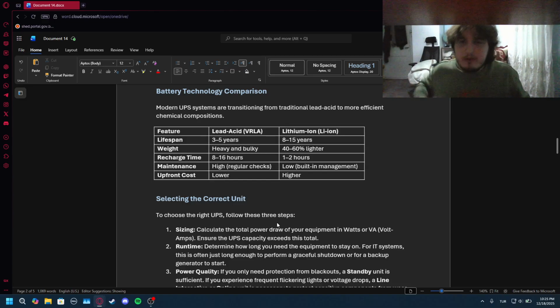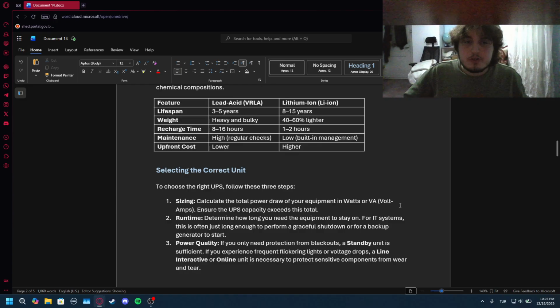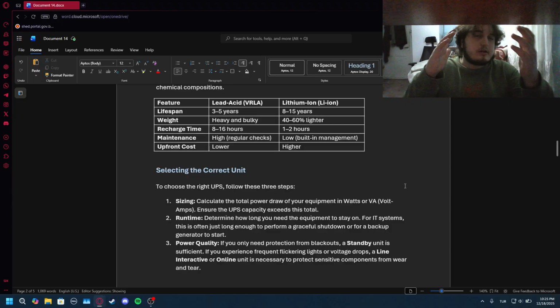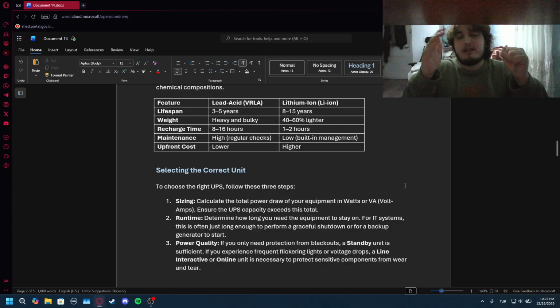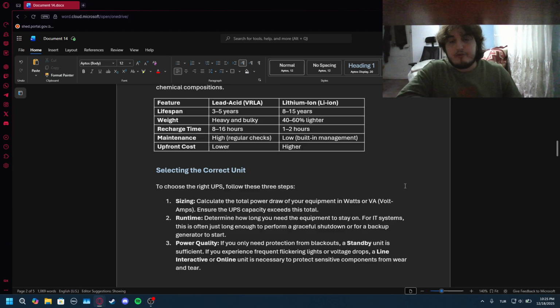To choose the right UPS, follow these three steps. Sizing: calculate the total power draw of your equipment in watts or volt amperes to ensure the UPS capacity exceeds this total, because it needs to exceed it so it can power itself. And obviously, if it's at that limit and you need a little bit more power, you're just not going to get it. Then the system is going to fail again. Or you're going to draw over voltage, and that's also bad for the UPS.